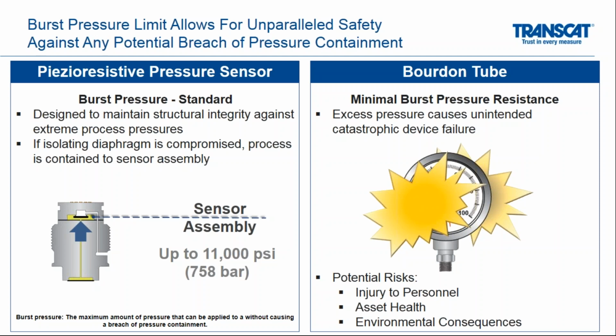Going over to the bourdon tube, there can be minimal burst pressure resistance. It's one of the reasons why many bourdon tubes are designed to blow out the back. So if an operator or any sort of worker were looking at the gauge and all of a sudden it would blow out, it wouldn't blow out in their face. This is not something that even needs to be considered really with the wireless pressure gauge, because that pressure resistance is up to 11,000 PSI, nowhere near where most bourdon tube gauges would be. Again, it's a potential risk for injury of your personnel, certainly for your asset health, and then there's environmental consequences depending on what gets leaked out.